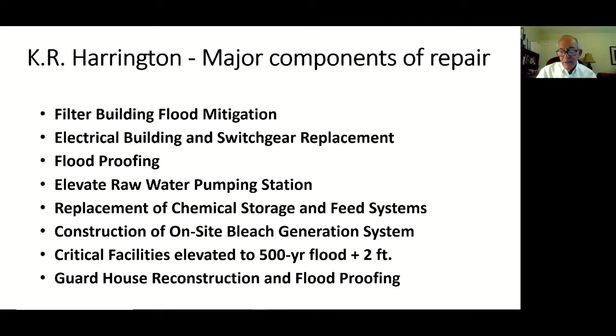We built an entirely new electrical building and switchgear system at a much higher elevation, and elevated the raw water pumping station by about four feet. All chemical storage and feed systems were replaced. We built an on-site bleach generation system, part of a long-range plan to eliminate the handling of hazardous materials. By generating bleach on site, we eliminate the need to handle gaseous chlorine. Critical facilities were all elevated to the 500-year plus 2 feet level.